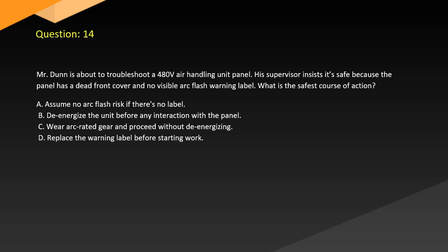Question 14. Mr. Dunn is about to troubleshoot a 480 volt air handling unit panel. His supervisor insists it's safe because the panel has a dead front cover and no visible arc flash warning label. What is the safest course of action? A. Assume no arc flash risk if there's no label. B. De-energize the unit before any interaction with the panel. C. Wear arc-rated gear and proceed without de-energizing. D. Replace the warning label before starting work.